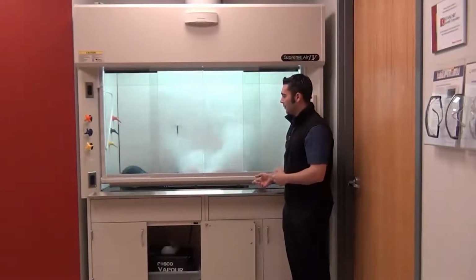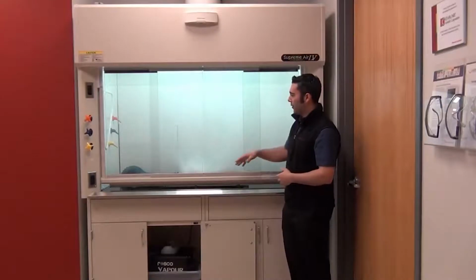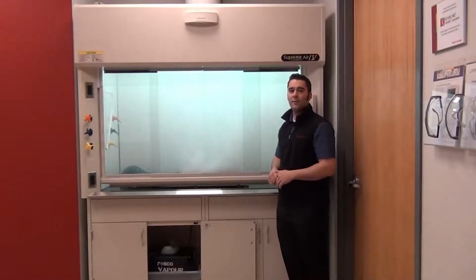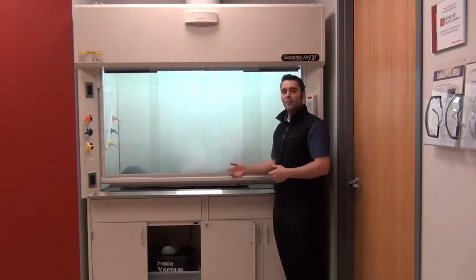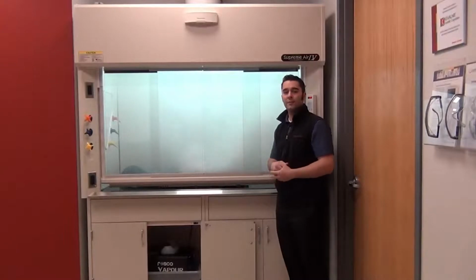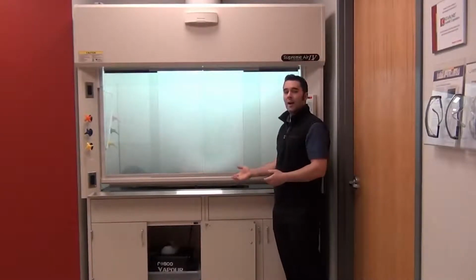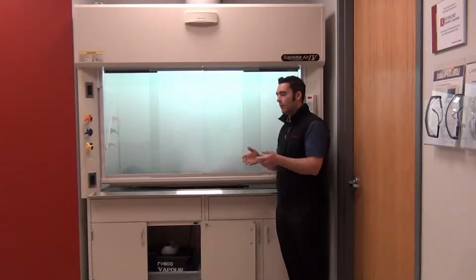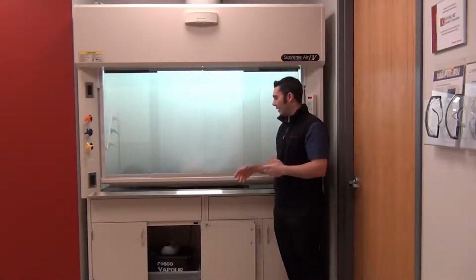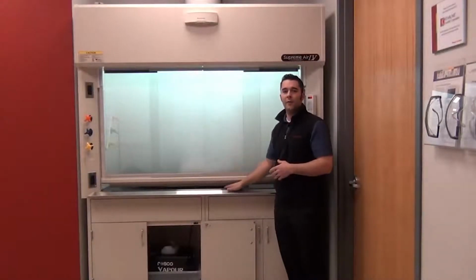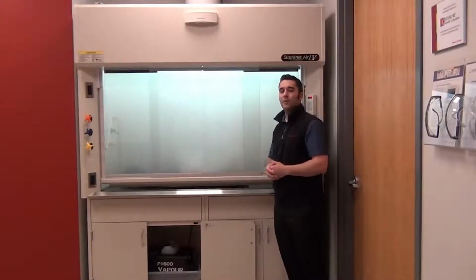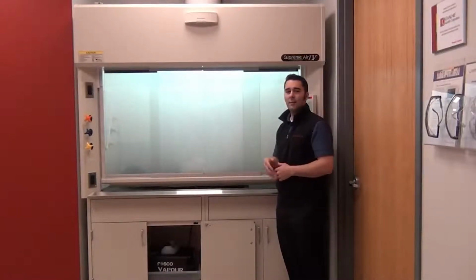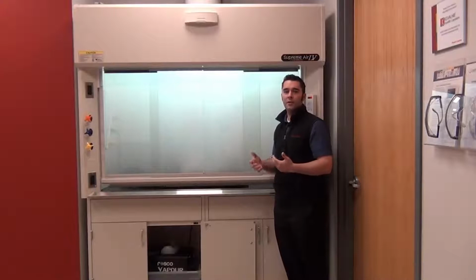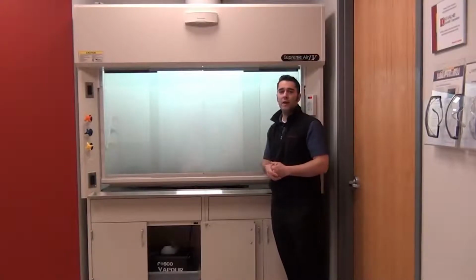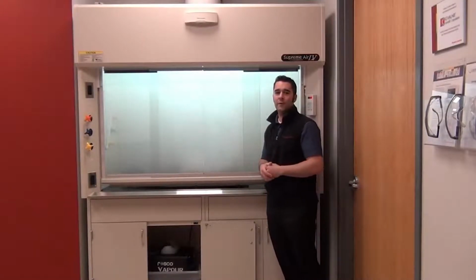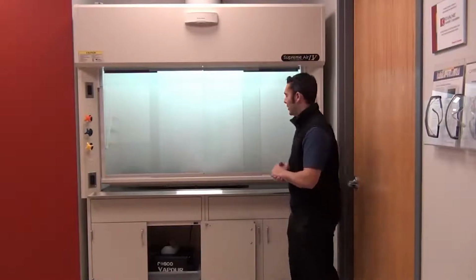So I'll show that as well. You can see the air is blowing around very quickly inside of the fume hood. So effectively what happens when I close the sash with a 3 second speed of response, I get a very high spike in velocity going into the hood, which again, if I had beakers or paper or something on the front of this hood, I could be knocking those beakers over. I could be causing chemicals inside of the fume hood to mix when they shouldn't be, and it could be affecting the reactions that I'm trying to do inside of my fume hood. So that's a 3 second speed of response.